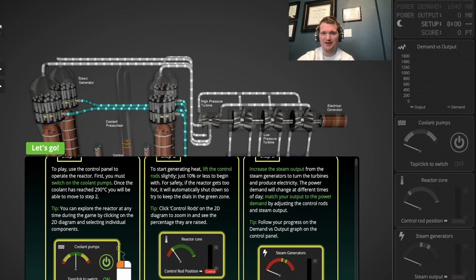I can tell this isn't modeled by the game. And it can be kind of a pain, because if you lower reactor power by, say, 50%, you're gonna have a peak of xenon hours later. A rule of thumb is it's the square root of your percent reduction. So you cut power by 50%, square root of 50 is about 7. So in 7 hours, you're gonna have a xenon peak that's gonna bring down power even further.